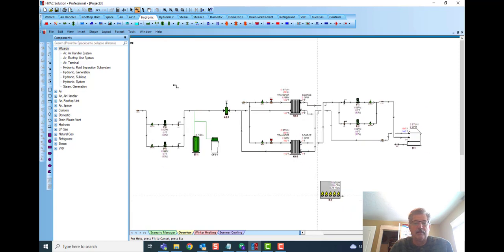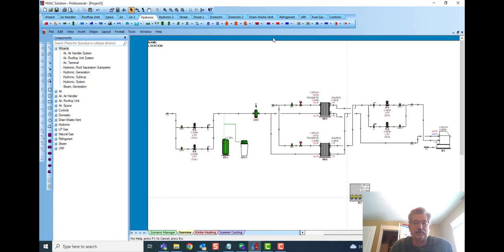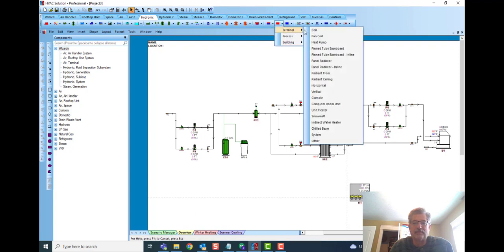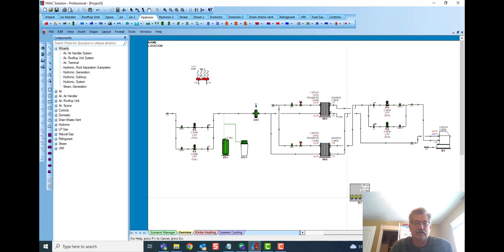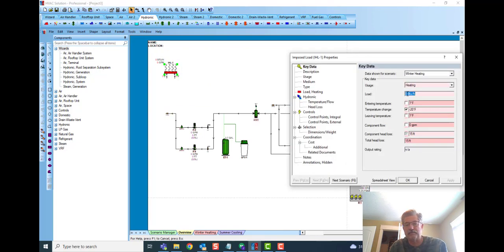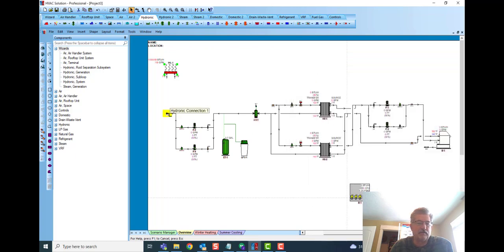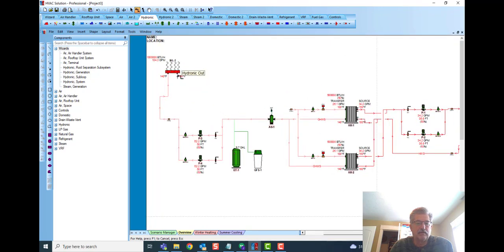connect in. Then now since I set a Snowmelt system, I'm going to come to the imposed load. And all these imposed loads, remember, they're just different pictures. So there's fan coils and radiant ceiling. We'll go down to Snowmelt. So it's just a different picture. I can come in there, component, click on that, type in a load, so many BTUs. So a Snowmelt system, you'd have like 100 BTUs per square foot on maybe a typical system. Multiply that by your area. We'll come with 1,000,000 there, put that in, connect that into the system, do the return.